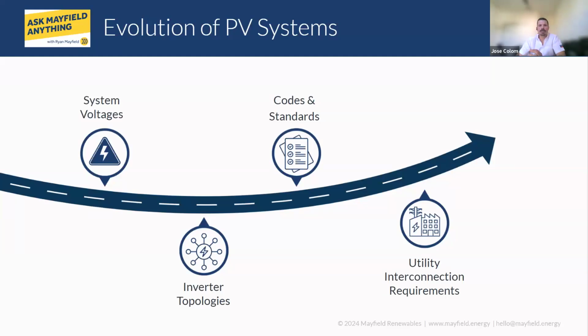Not at all, from our end. When we look into this system, we consider not only arc fault but also ground faults. Nowadays, newer inverters offer both capabilities. So our inverters, before starting operation, look for ground faults, and if the measurement is within limits, the inverter starts operation, and during operation it keeps on measuring. Same thing with arc fault—if there's any arc fault detected from the DC side, the inverter would cease operation, point out the fault, and then restart. So it's not an issue we've seen. It's not the first system out there—we have quite a few systems going, and no issues.